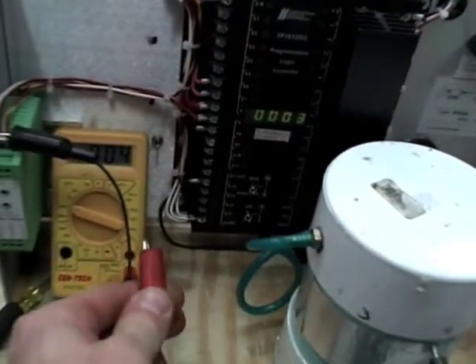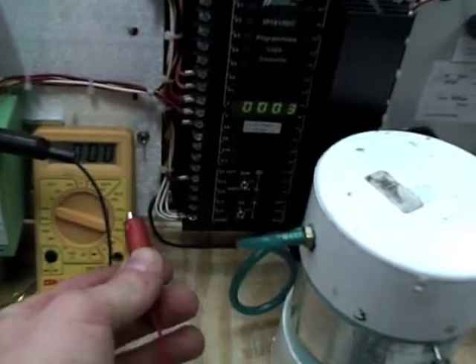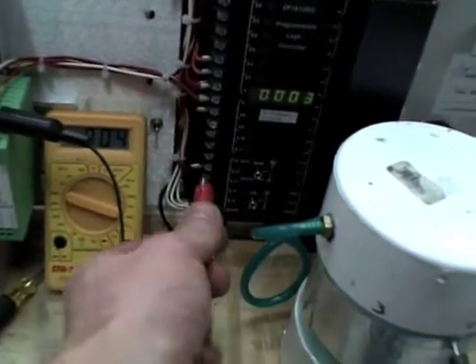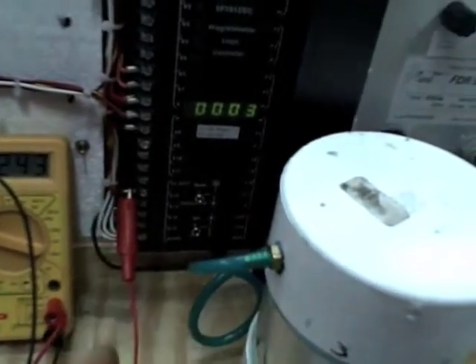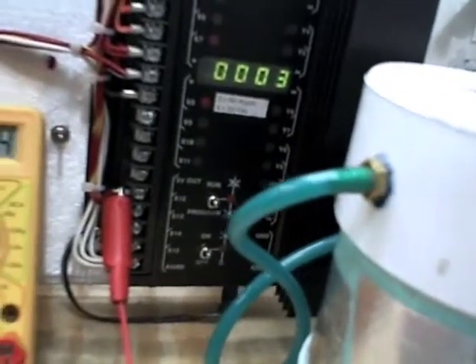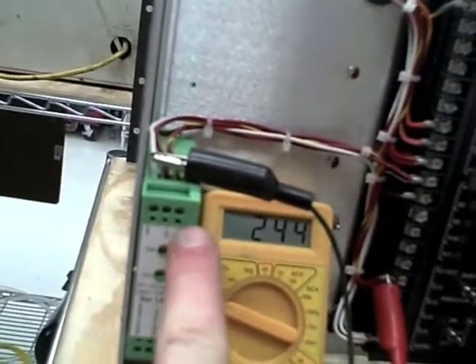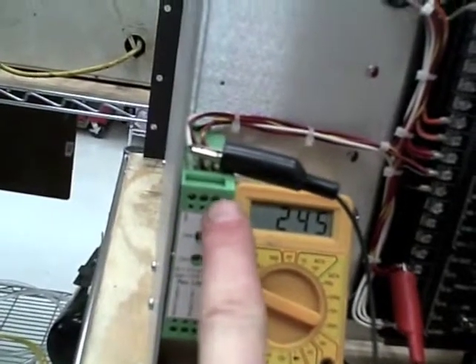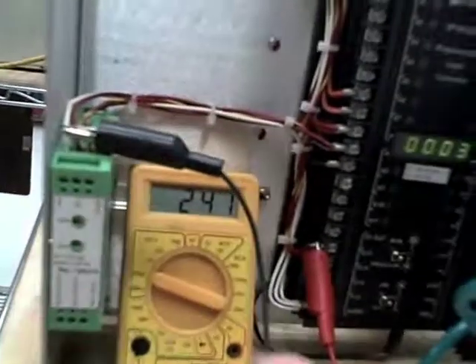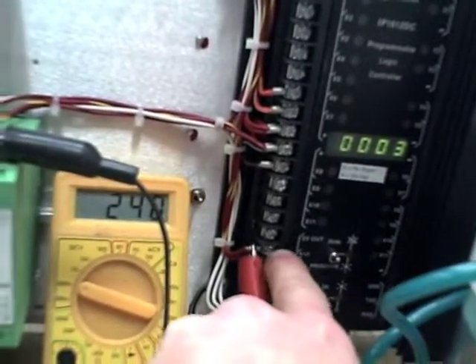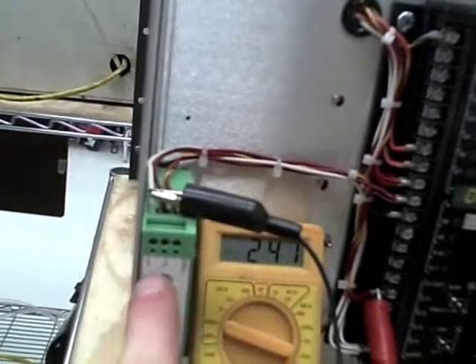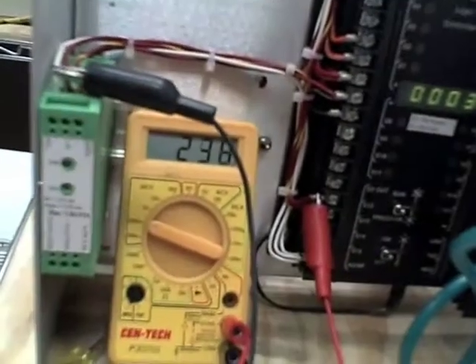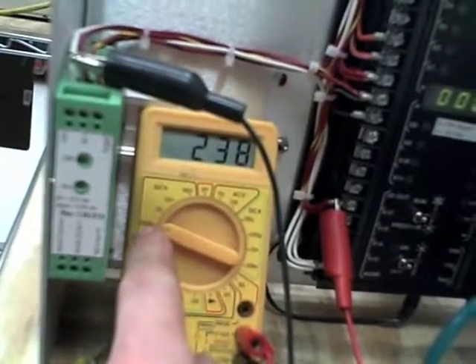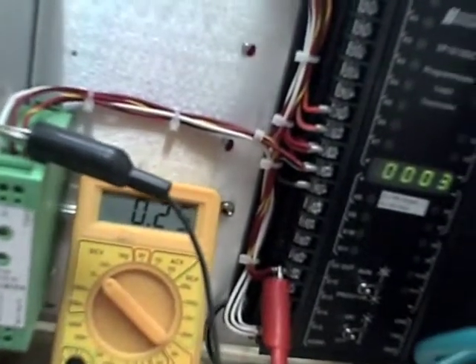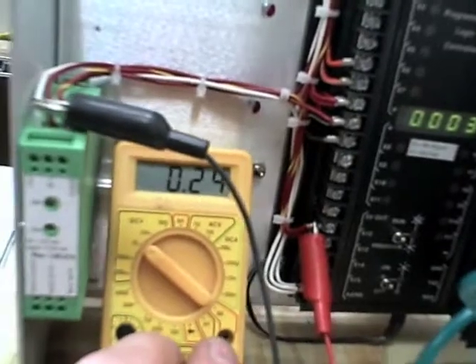Now I removed my red lead from the voltmeter, from the amplifier board, sorry, and I'm going to actually put this over here now on the PLC, and it'll be X12 on the PLC. You can also connect the red lead to the output screw on the amplifier board, but just again for simplicity, while I'm just doing this with one hand, I'm going to be just putting the clip on X12, and I'm going to leave my black lead on the common. I'm just going to leave it right there. Now I'm going to take my voltmeter and go from 2000 M to 20, and what that's going to do is give us a different range for our voltage readings.